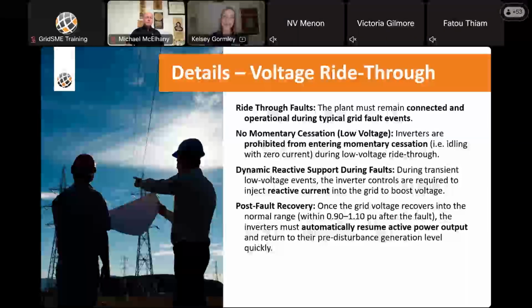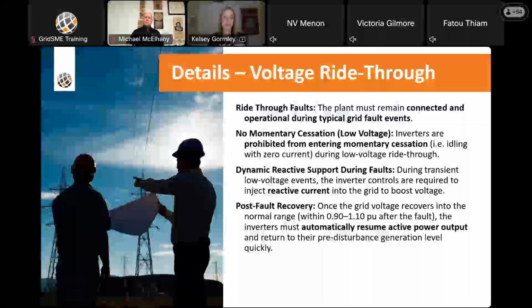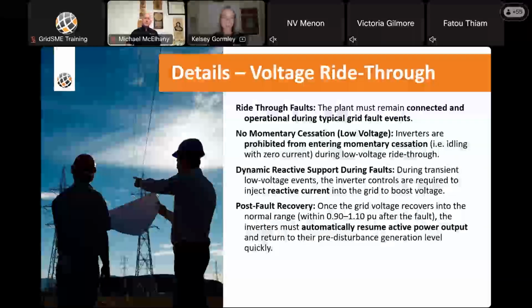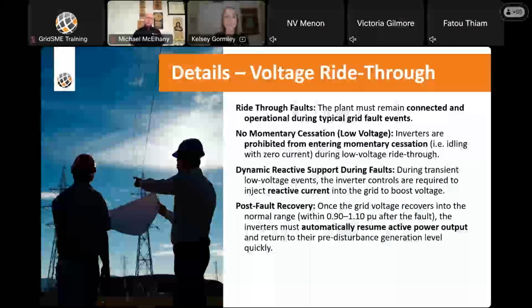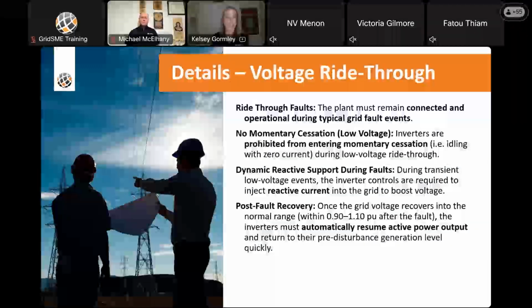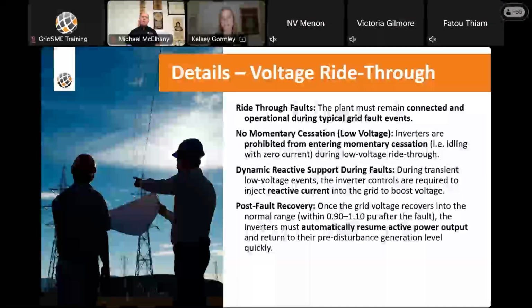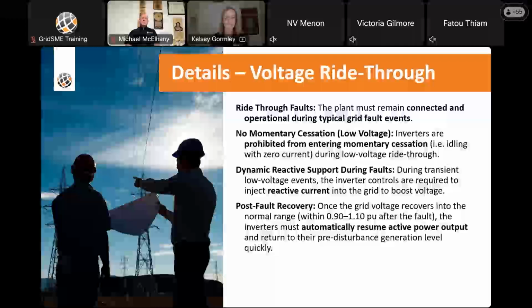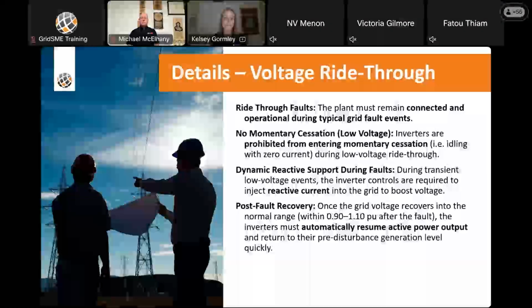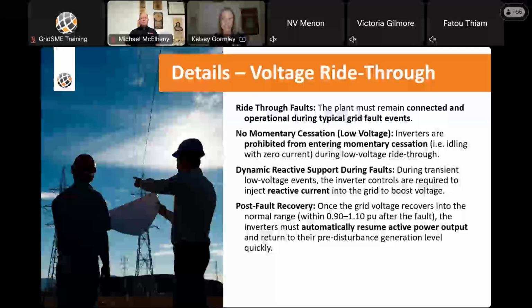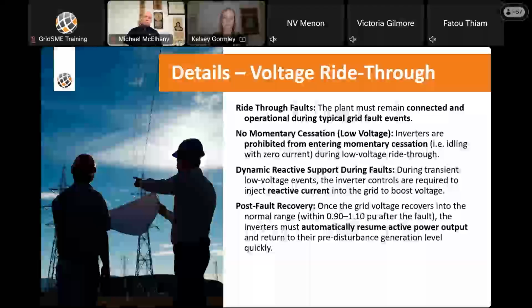In addition, Appendix H does mandate rapid ramp up of inverters, which should restore the output at a rate of at least 100% of capacity per second, achieving the full pre-fault output less than 1 second after voltage is back to normal. So that's the fast response component of this. Even if the inverter has momentarily reduced output or has ceased current for a high voltage transient, it must come back online within 1 second. This fast recovery ensures, again, that the grid does not experience a prolonged generation shortfall once that fault has been cleared.